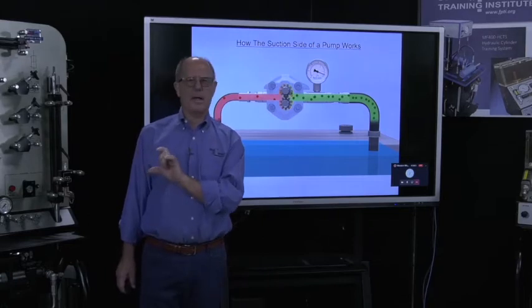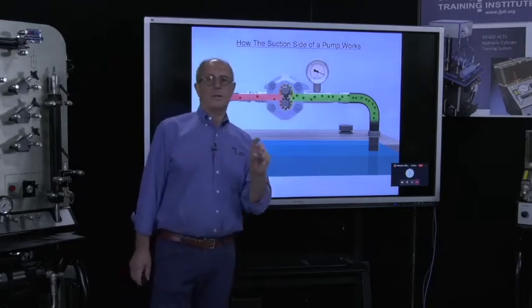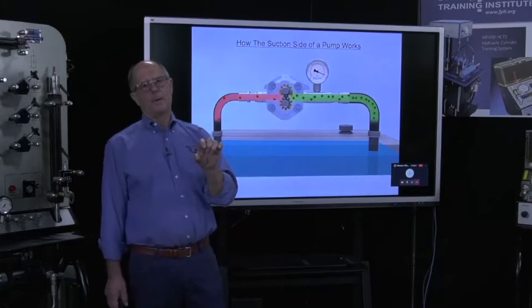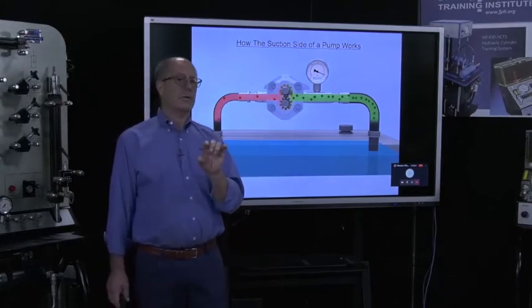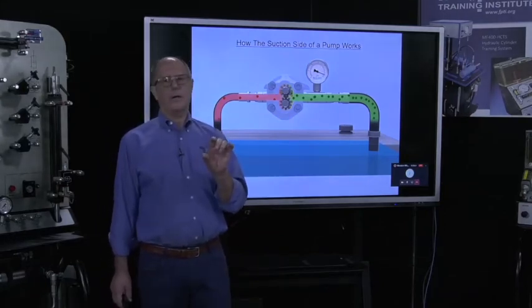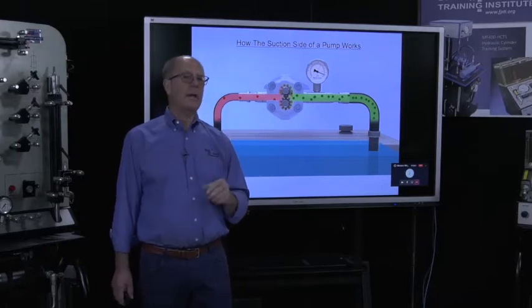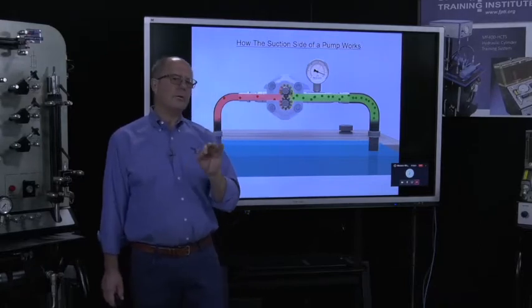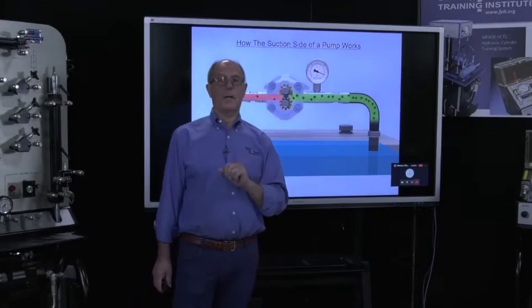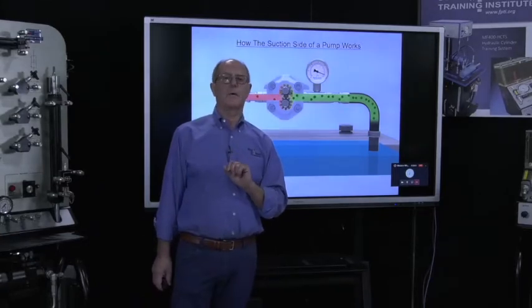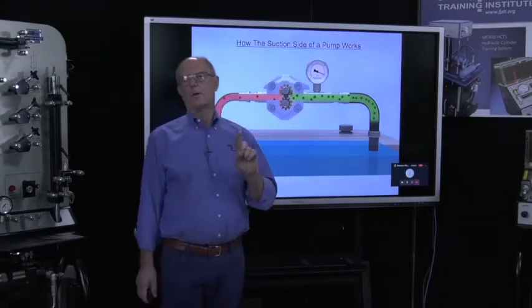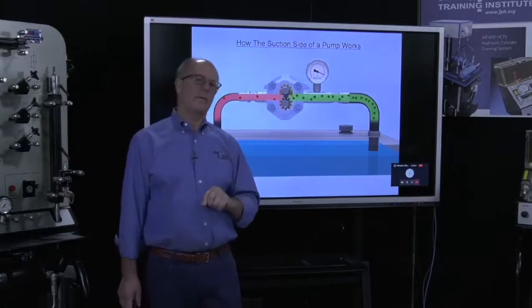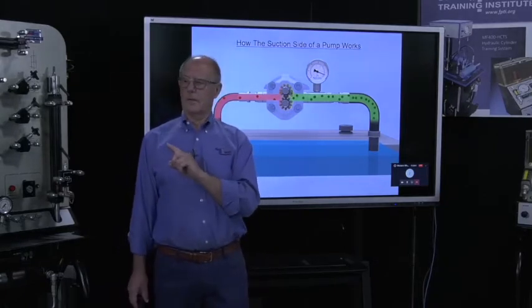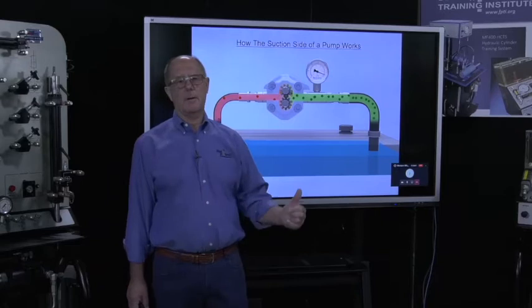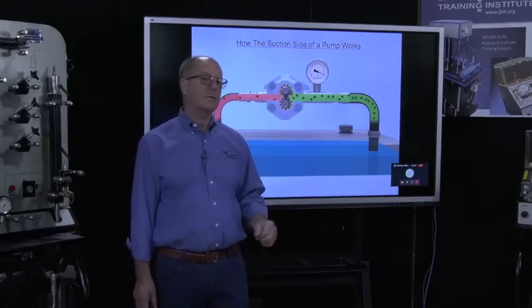What does a vacuum gauge do? If there was a place on the pump, on the intake of the pump, where I could check inlet restriction every 30 days, then I wouldn't have a problem looking at the screen. So when you're checking inlet restriction on a pump on a routine maintenance basis, you're looking at a number of things. One is the condition of the breather on the hydraulic reservoir, because if the breather starts to plug, it's going to show up as a problem with inlet restriction.